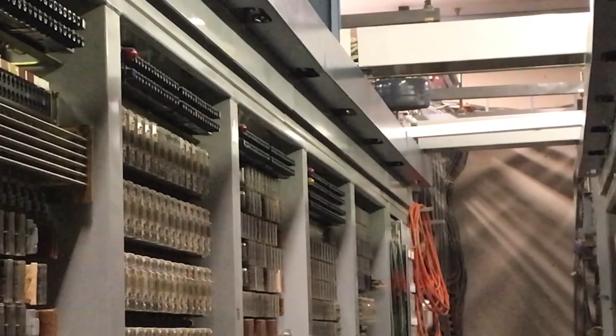In your large central offices, step-by-step XY and crossbar switching systems, generally they would have one main fuse for the entire aisle, and all of the secondary fuse panels would be tapped into that one particular lead, and it may be fused at 300, 400, 600 amps depending on how long the aisle was and how much equipment was in that aisle. They no longer do that in any of the modern central offices. Every relay rack, or bay as it's referred, has its own BDFB fuse. So in this case that I built, I have an individual fuse for every single relay rack.